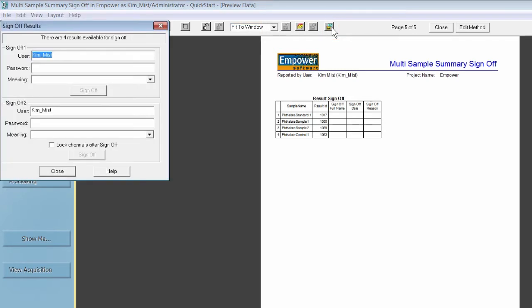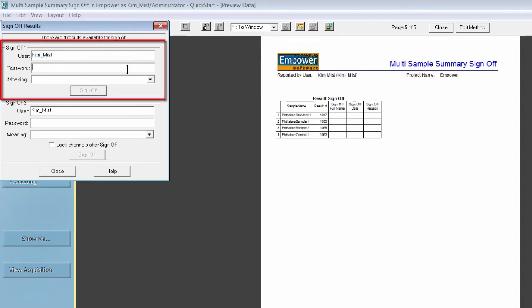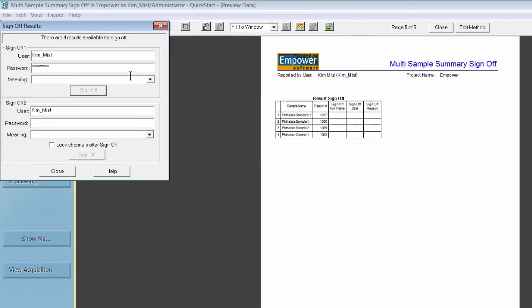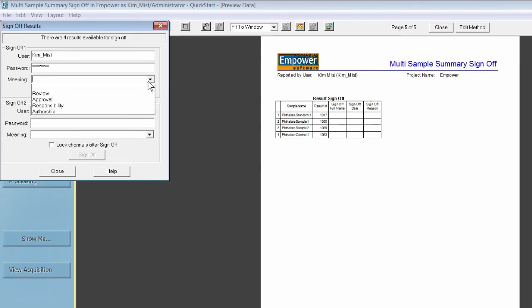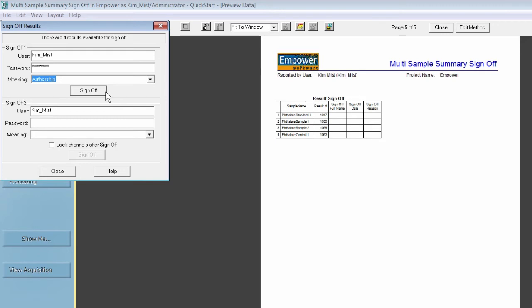The Sign-off Results window opens. From here, you can see the number of results you are signing off. Determine if you are performing sign-off 1 or sign-off 2 and then enter in your password. Select the meaning or reason you are signing off on the results by using the drop-down menu or by entering it in. If required by your policies, select Lock channels after sign-off. To complete electronic sign-off of the results, click Sign-off.